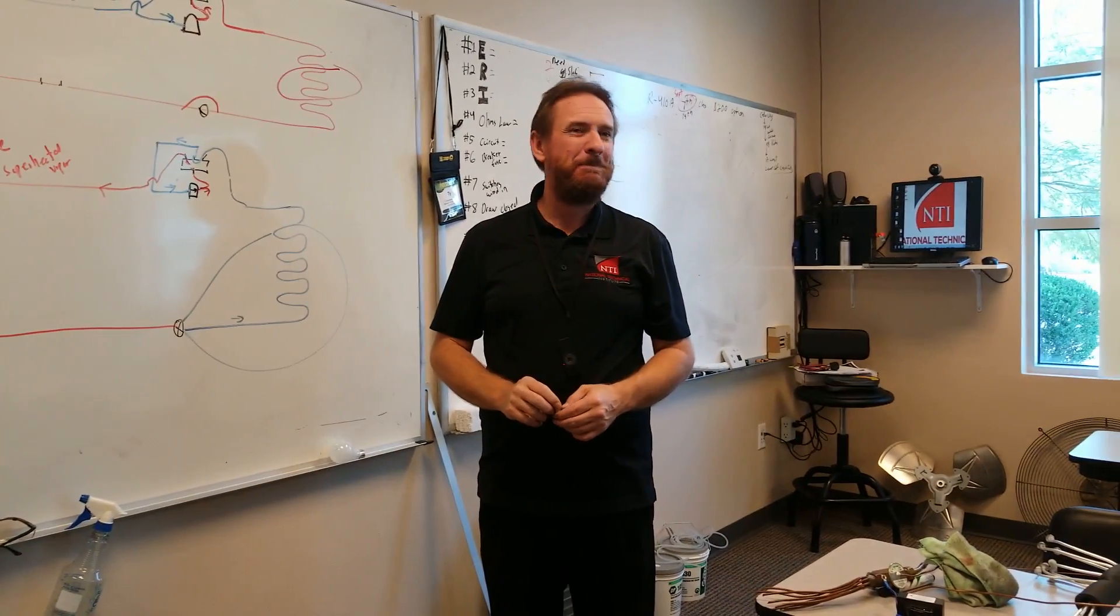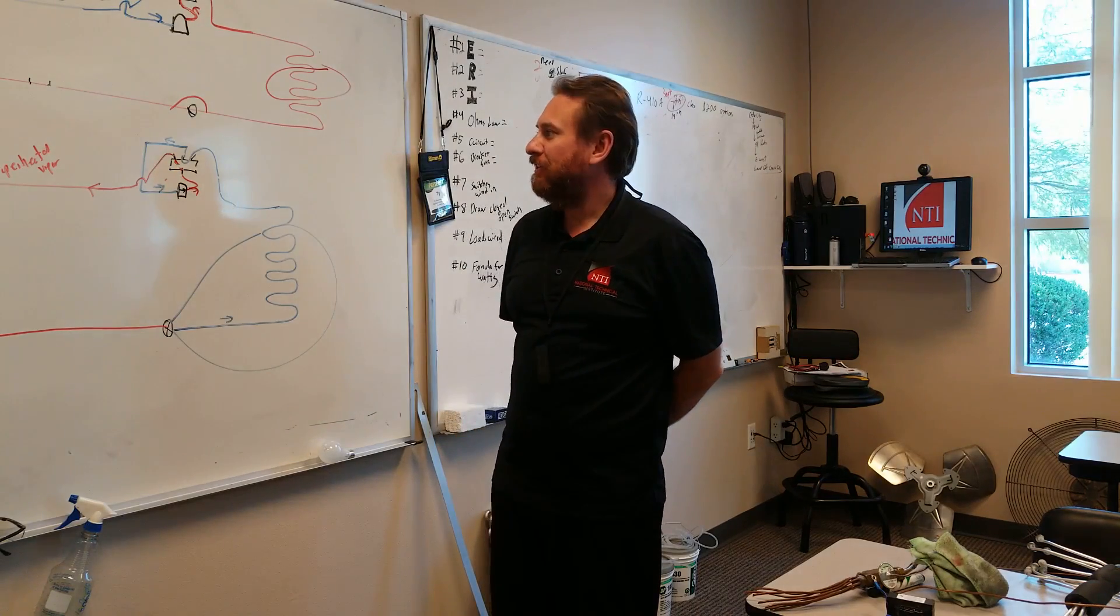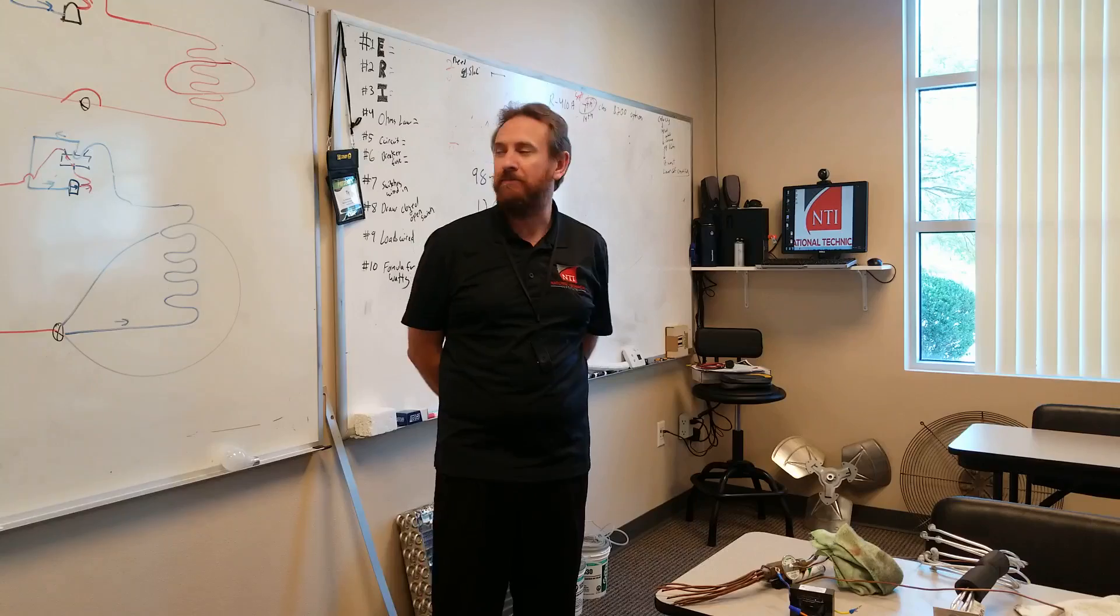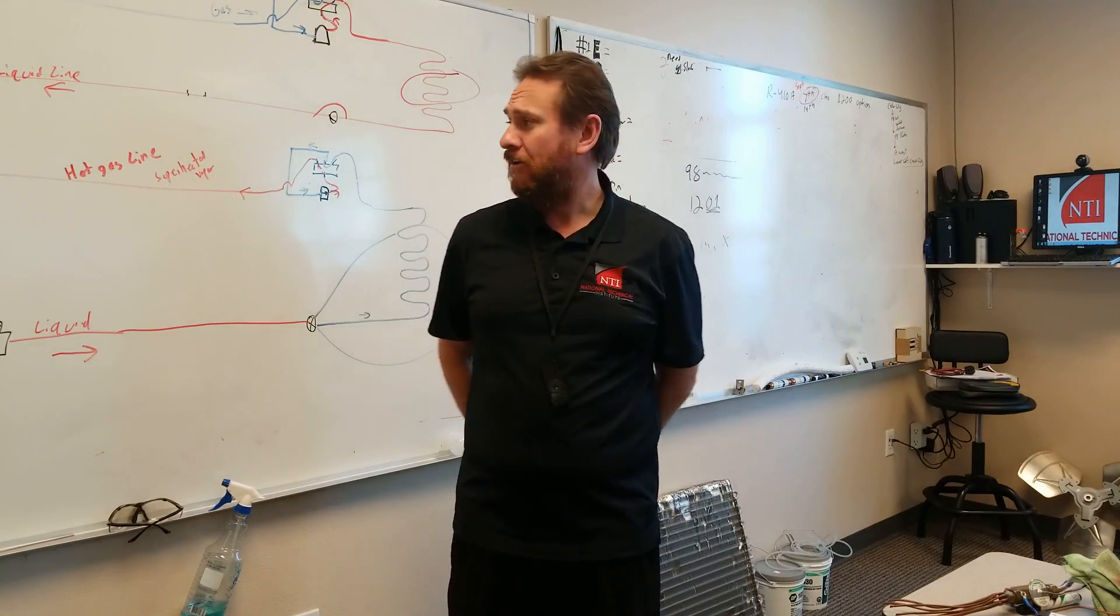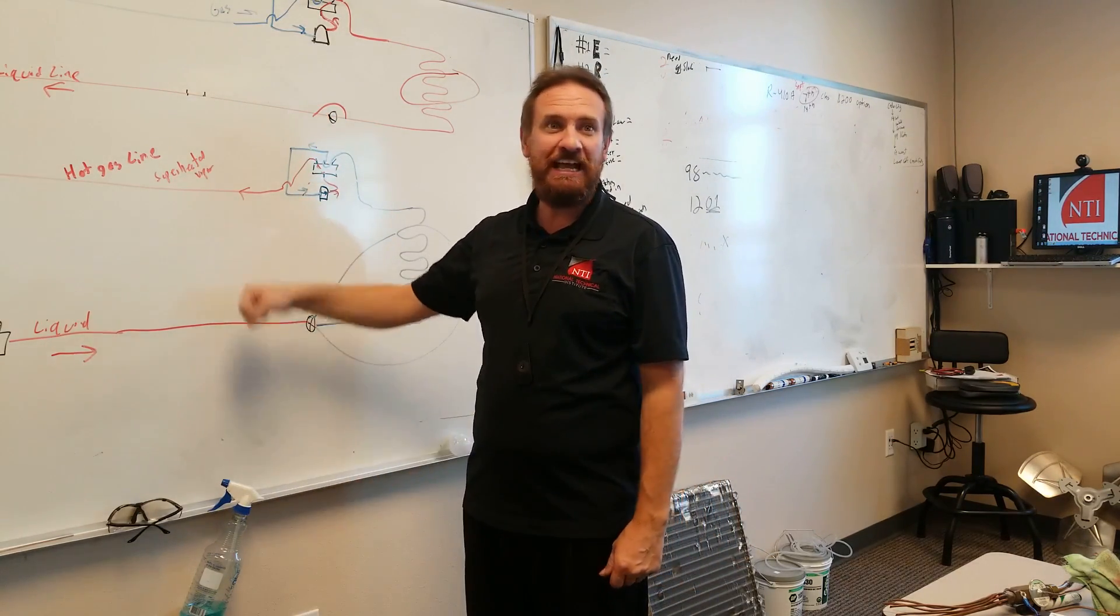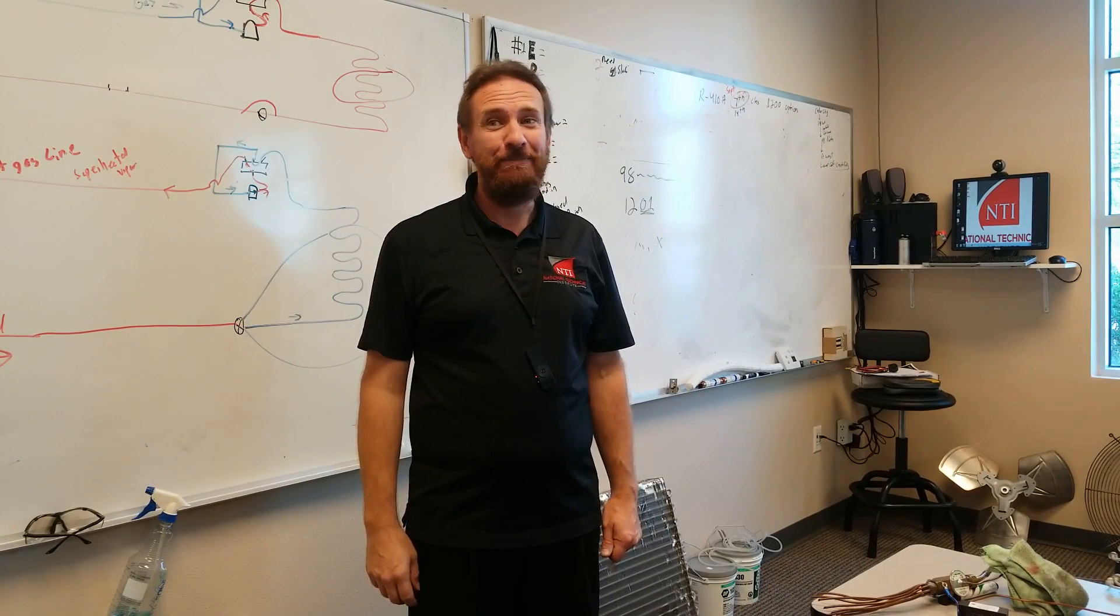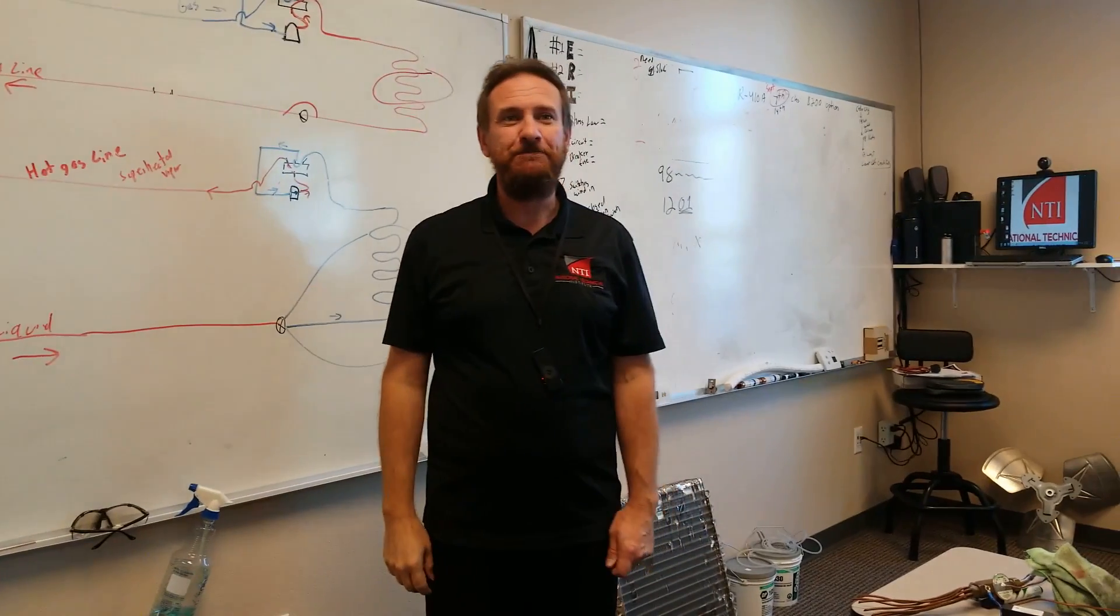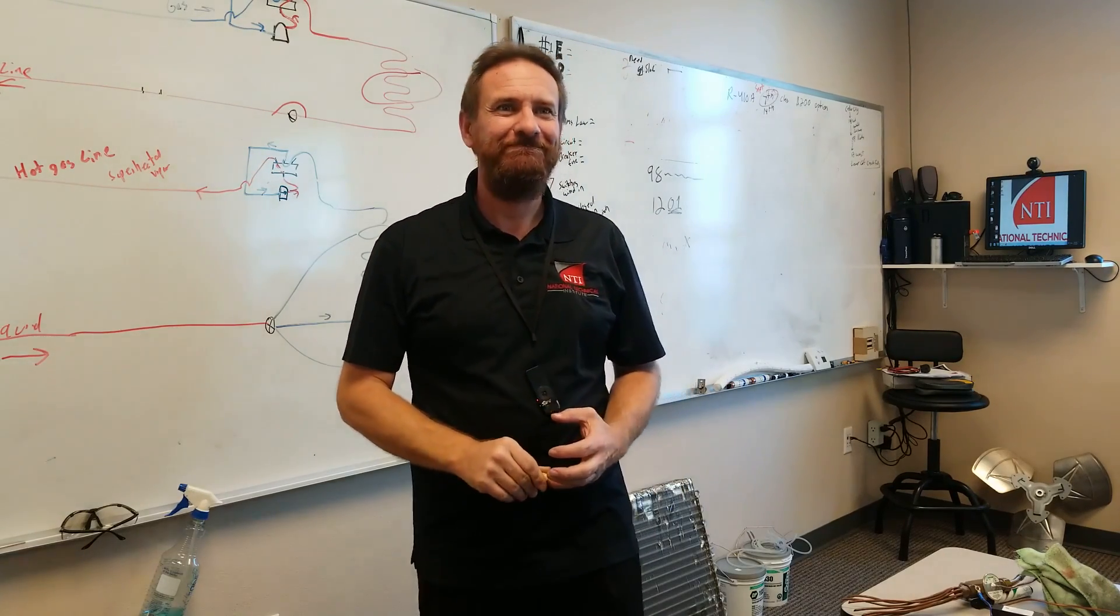All right. Questions? It's pretty simple. It is. It's very simple, right? It's very simple. The big thing is that people just don't understand what that part is, and they try to guess on it and assume that that's the problem, and it's rarely the problem. You just simply measure the temperature on those lines, and you can tell if it's leaking or not if you think that's what it is. And then, oh, what mode is it in? Well, here's a good way. How about this gas line? It's summertime. You touch that gas line. Ow, it burned me. What mode is it in? It's in heat pump mode. It burned you. I touch the gas line. Oh, it feels cool. What mode is it in? It's in AC mode.